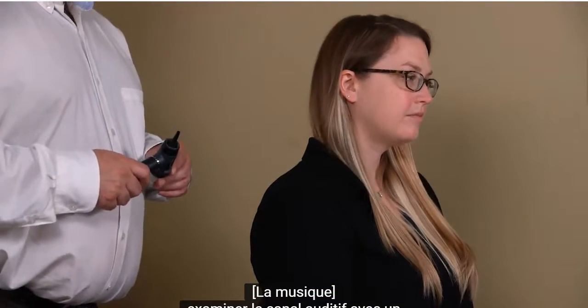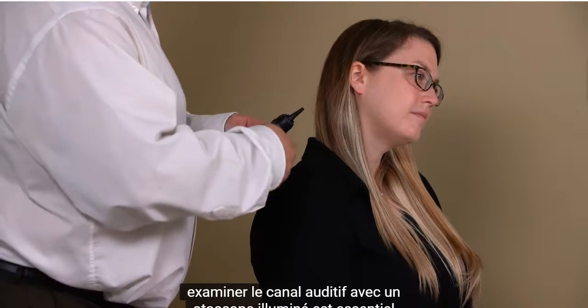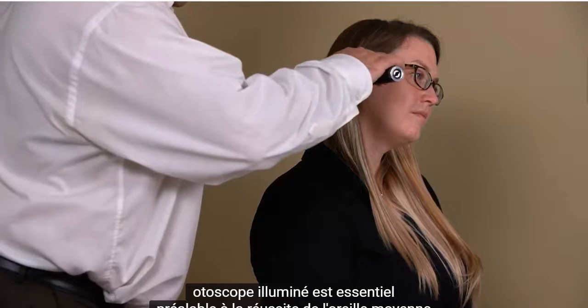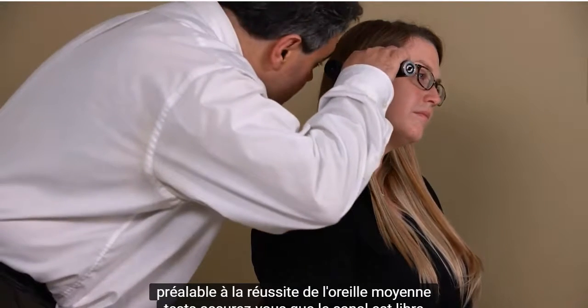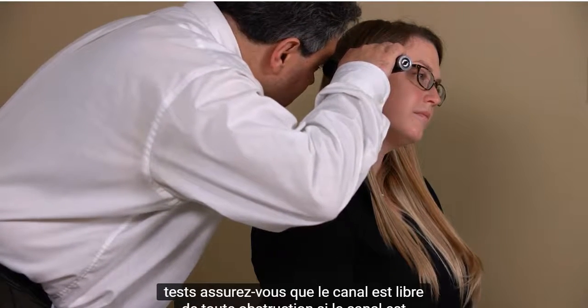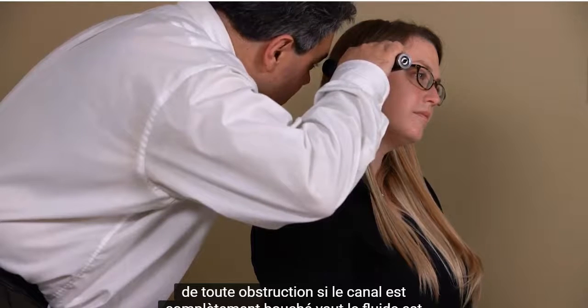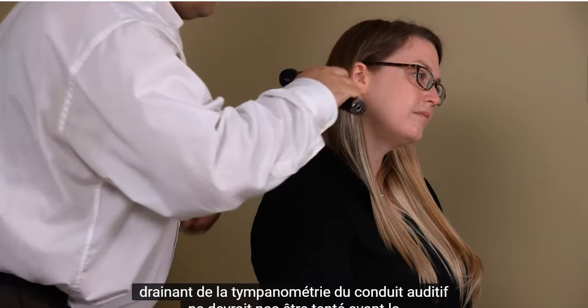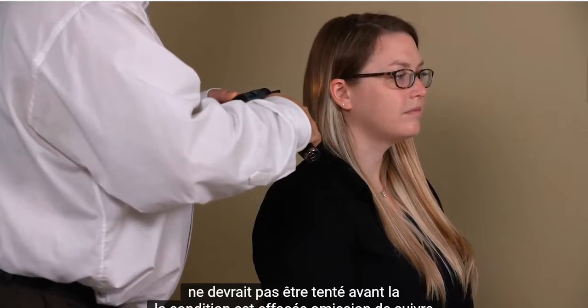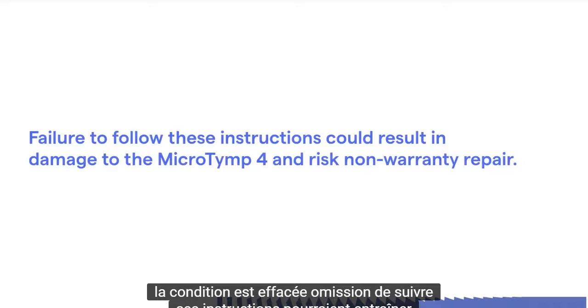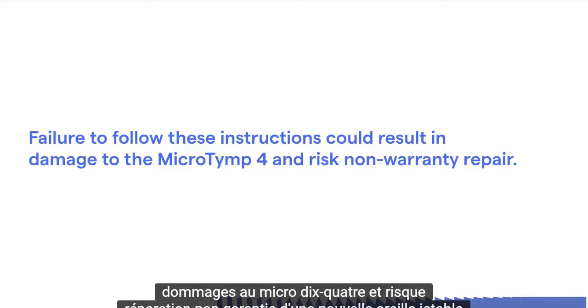Examining the ear canal with an illuminated otoscope is an essential prerequisite to successful middle ear testing. Make sure that the canal is free of any obstruction. If the canal is completely plugged, or if fluid is draining from the ear canal, tympanometry should not be attempted until the condition is cleared. Failure to follow these instructions could result in damage to the MicroTymp 4 and risk non-warranty repair.